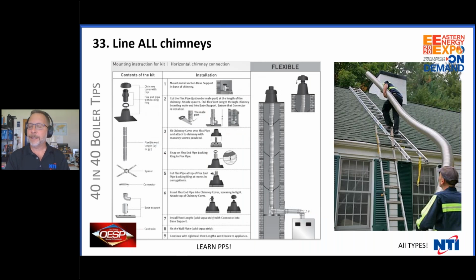Line all your chimneys. I had a chimney sweep come into my office one day and thank me. He thanked me because I was using a rule of thumb back then that said if your chimney with an 82% efficient gas boiler or 87% oil-fired boiler, we used to have this rule of thumb. If the chimney was in the center of the house, you never needed to line it. If it was one side exposed to outside, you don't have to line it. If it's 3 sides exposed to outside, you have to line it.